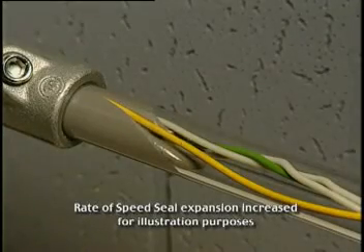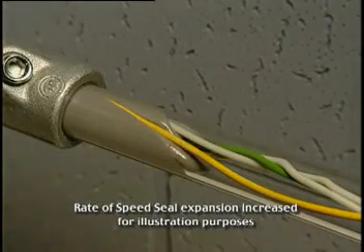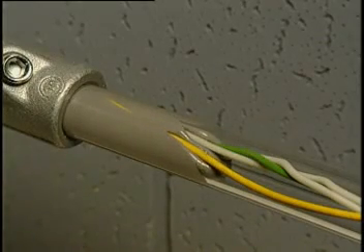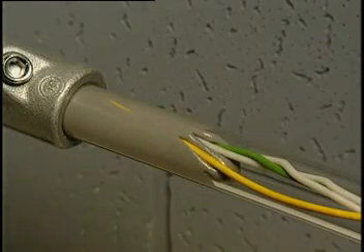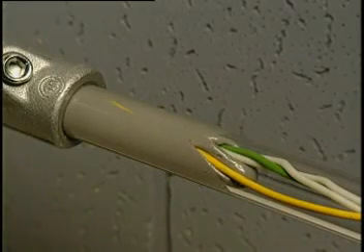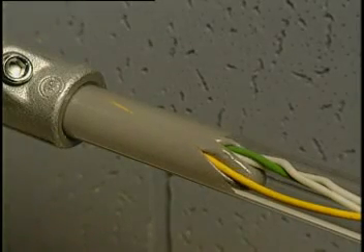The secret to the success of the Chico Speed Seal is that it expands to four times from its original liquid state. The expanding compound physically separates the conductors while it completely fills and hardens in the fitting in both warm and cold temperature conditions.